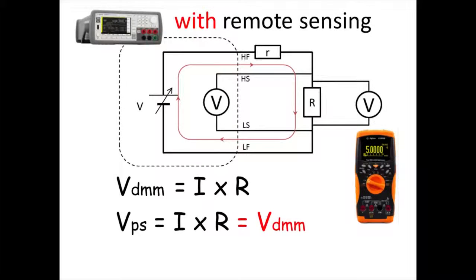In case you use remote sensing, the power supply can monitor the applied voltage of the DUT using sense terminals instead of force terminals.